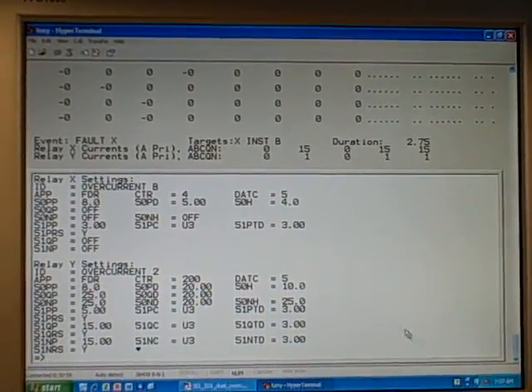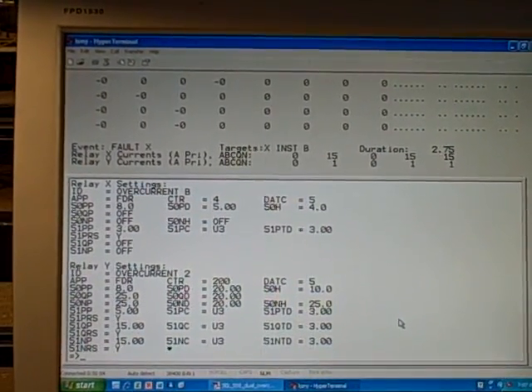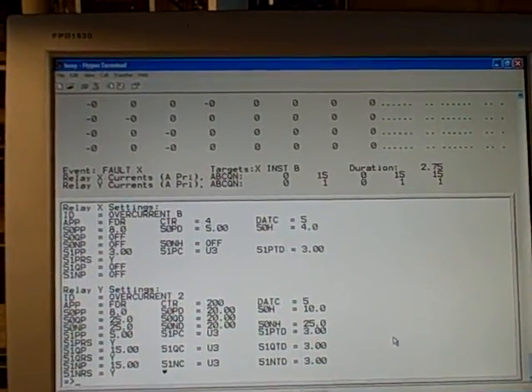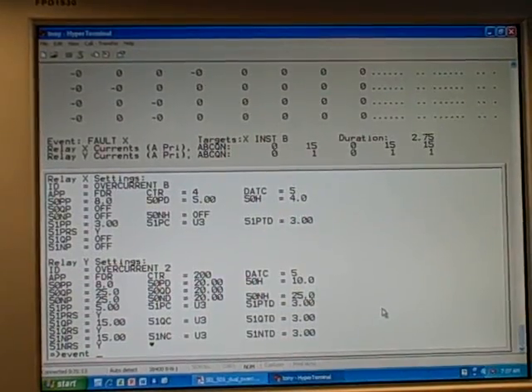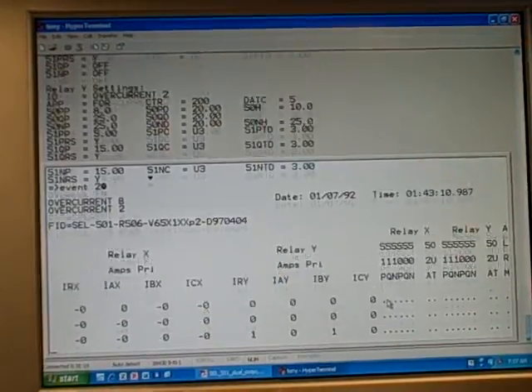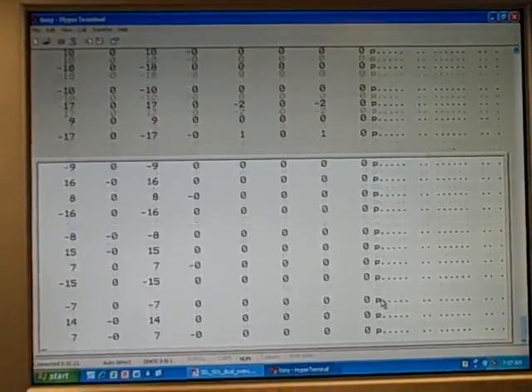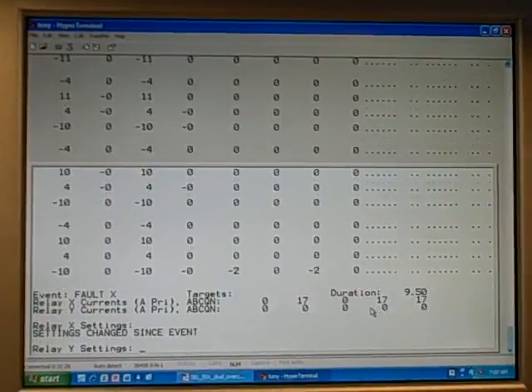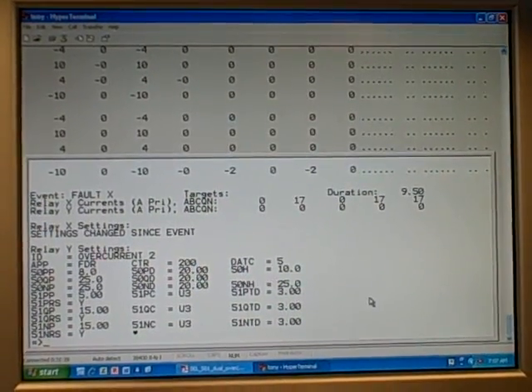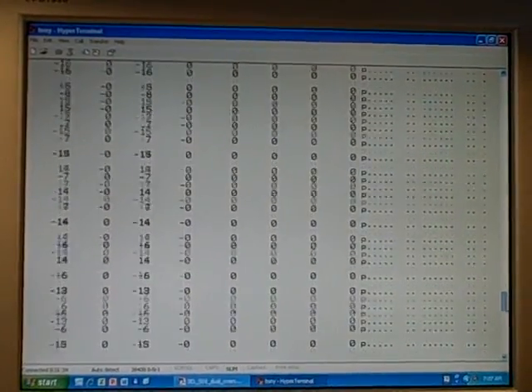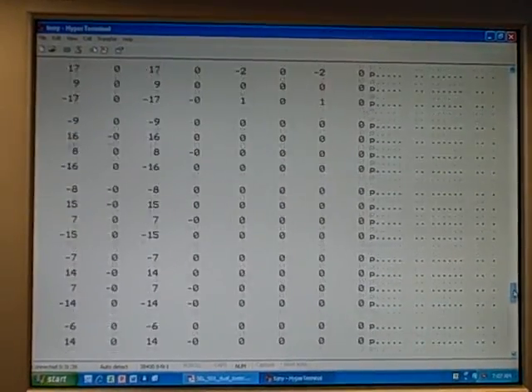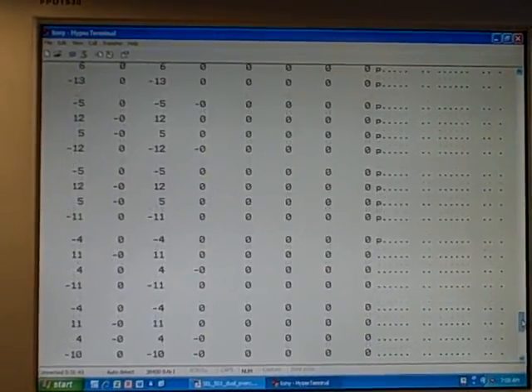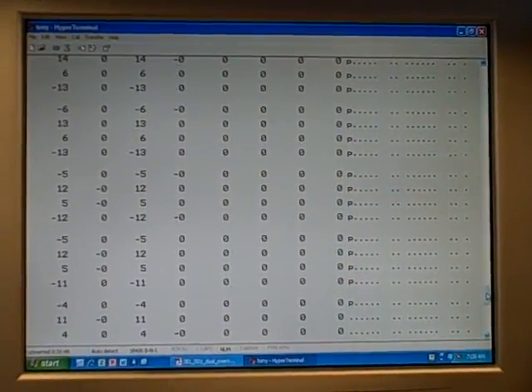Another interesting thing to bring up here is that this particular relay keeps a record of a number of events, not just the latest one. So if I wanted to recall the event that happened before this, which was the event where it actually picked up the time over current element but it didn't trip, I can go event two. That looks back in history at the previous event. If I typed in event three, it would look at the event three times back, or event four, the fourth event back in time. So this relay actually holds a number of event histories, which you can review using the serial connection, in this case using hyperterminal to talk to the relay, or if you want to use one of SEL's software products like AcSELerator, you can do that as well and review the events. You can even store the events using that software, store it to your PC for further analysis.